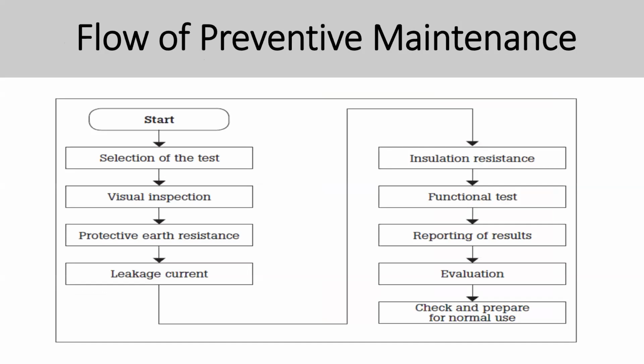So when you talk about preventive maintenance, normally when you start, you need to know what tests you're going to do: basically electrical safety, performance tests, visual inspection. So basically you're going to do visual inspection, protective earth resistance, and leakage current. One of the main reasons you do protective earth resistance is that you want to make sure the RF leakage or any leakage should go through your plug point grounding. So you're going to do all these insulation resistance tests. It depends, you don't necessarily have to do them every time. Then functional tests, reporting of the results, evaluation, and check and prepare for normal use. These are common things that you're going to do during a preventive maintenance.